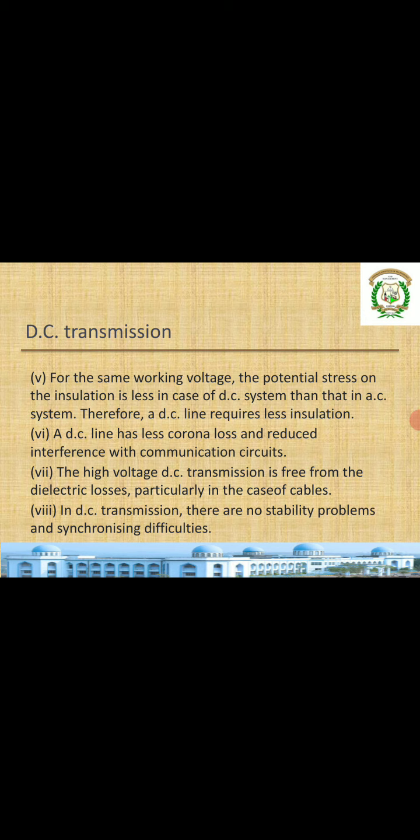For the same working voltage, the potential stress on the insulation is less in case of DC. In AC there will be more stress, so a DC line requires less insulation compared to the AC line. Also, a DC line has less corona loss and reduced interference with communication circuits.